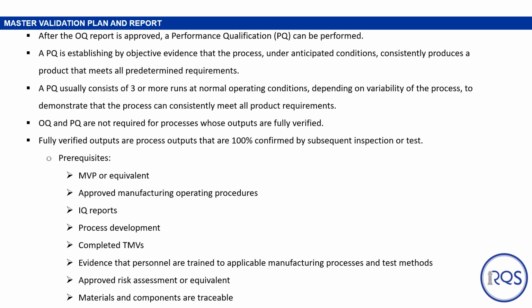After the OQ is approved, a performance qualification or PQ can be performed. A PQ is establishing by objective evidence that the process, under anticipated conditions, consistently produces a product that meets all predetermined requirements. A PQ usually consists of 3 or more runs at normal operating conditions, depending on the variability of the process, to demonstrate that the process can consistently meet all requirements. So again, we have the high and the low, and then we have normal somewhere in the middle. And so the PQ is typically the nominal in the middle.